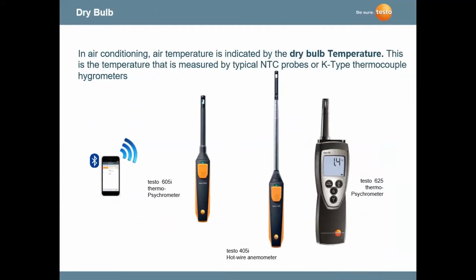Another measurement, and this goes back to air conditioning again, is a dry bulb rating. Obviously, dry bulb is ambient air temperature. When we measure, we use different types of probes, K-thermocouples and NTC probes, which I'll get to a little bit later, to measure temperature.